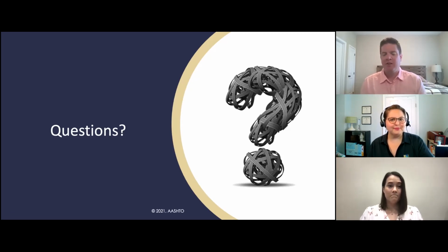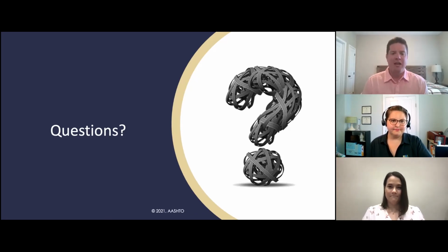I can jump in. It's a great question. The answer is no, you don't have to. The system that you have should work for you, for your laboratory. It should be easy to understand for you and your technicians. So if it all works for you to have it all together in one big list, that's great. The assessor, when they show up, will just have to look for the pieces of equipment that are pertinent to the assessment. But if it helps your staff to have a list that has a concrete section, a soil section, an aggregate section, and an asphalt mixture section, that's great too. Again, it's kind of what works best for you in your laboratory.